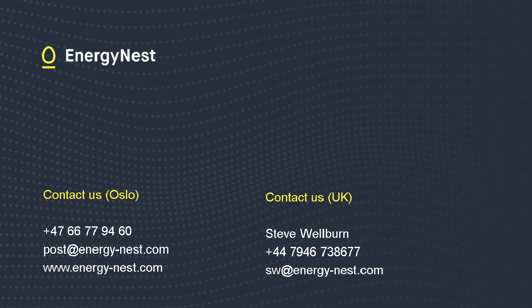Budila is asking, can the system be used to recover and store heat from a biomass boiler to heat the inlet feed water? Yes. Simple, quick answer, but of course, we would need to understand a bit more. But the answer is yes. If you have waste heat, you can accumulate that, and you can also use it to preheat feed water on the other side. But you can also reduce the extraction of steam extractions from the generator if you wish to do that. That's also another way to optimize or increase efficiency.